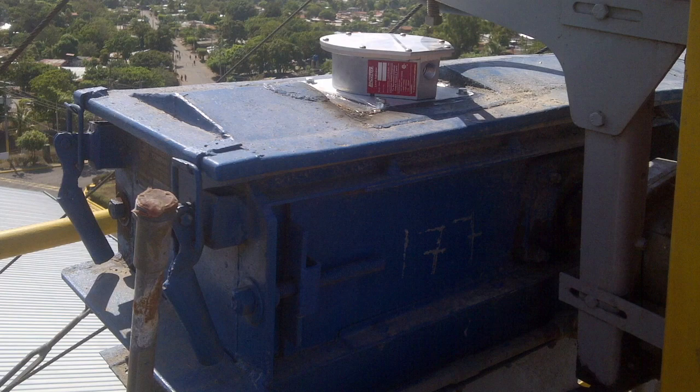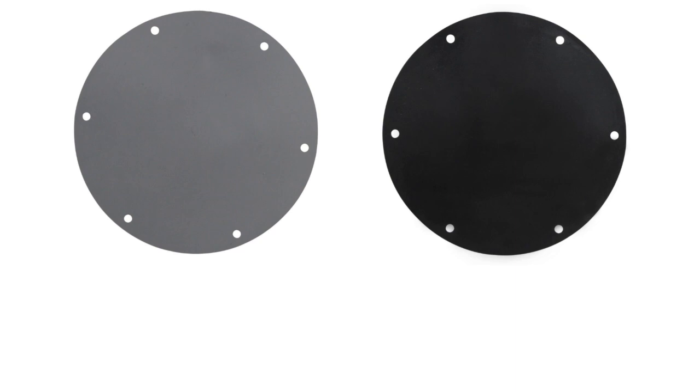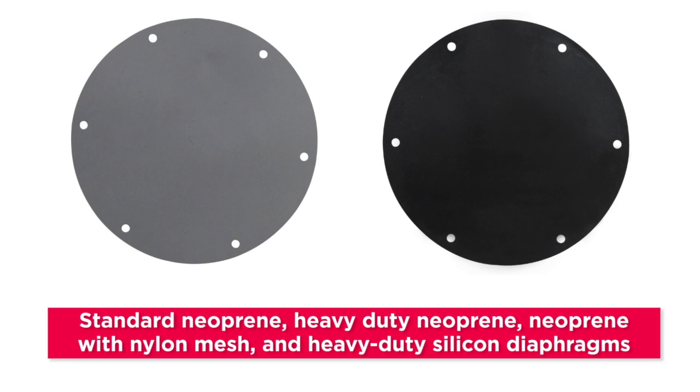The switch can also be built with a heavy spring and rugged diaphragm material and used for plugged chute detection. Standard neoprene, heavy-duty neoprene, neoprene with nylon mesh, and heavy-duty silicone diaphragms make these switches adaptable to many different materials.